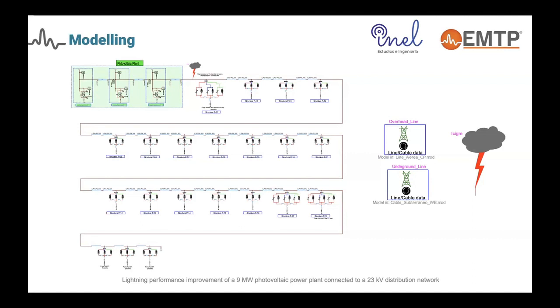We have a photovoltaic model representation that, as mentioned, does not take into account the electronics and control system, but does take into account the important aspects for this kind of study — which is the distances between equipment. Since we are doing a high-frequency overvoltage study, it is really important to take into account the capacitance of different elements, especially the transformer itself. We added a capacitive pi model topology to represent capacitance between windings to ground and between windings, which is the main aspect.